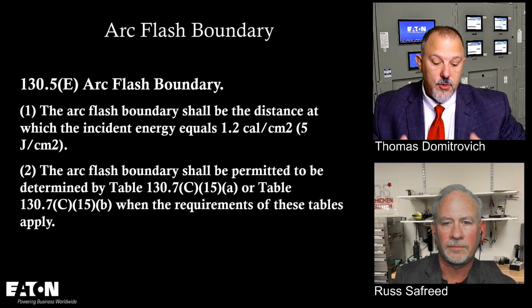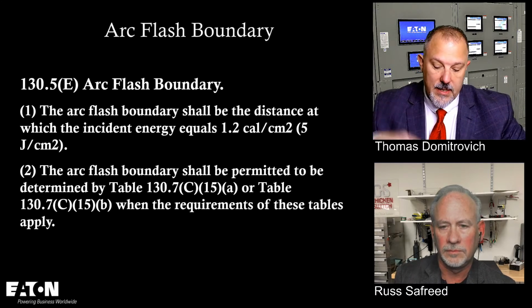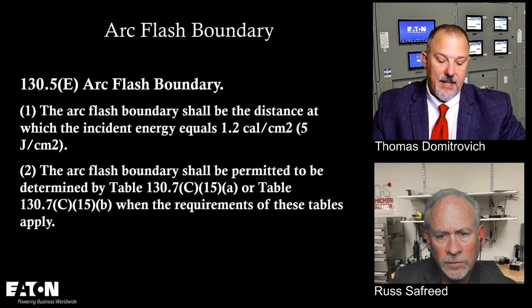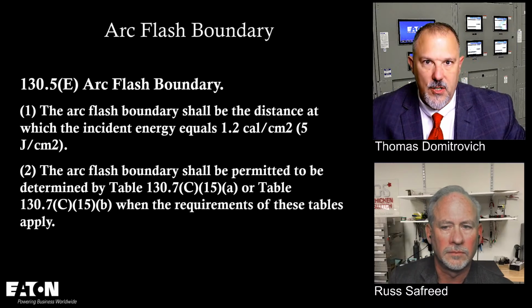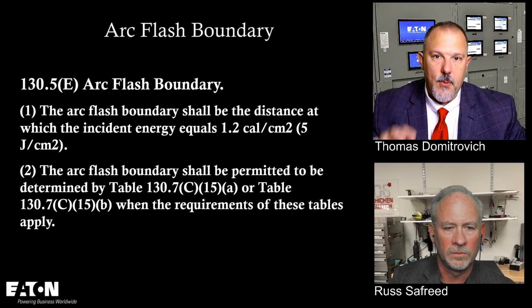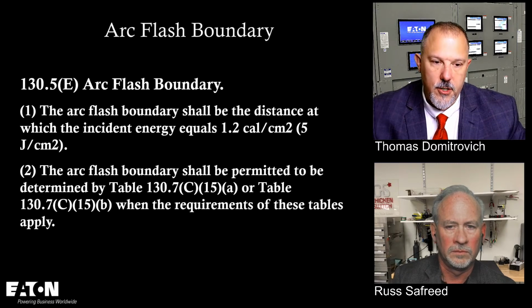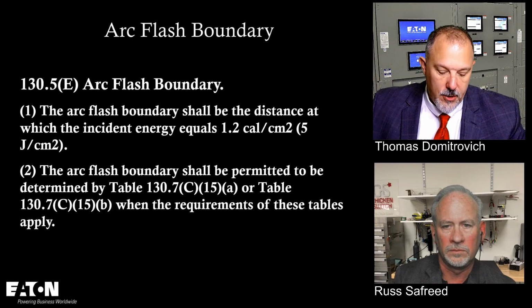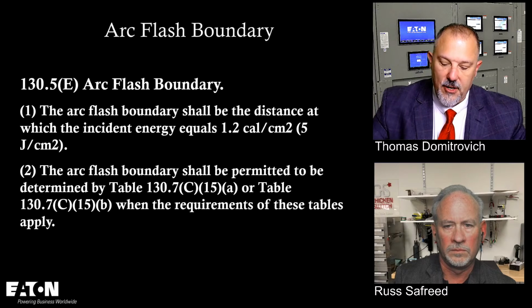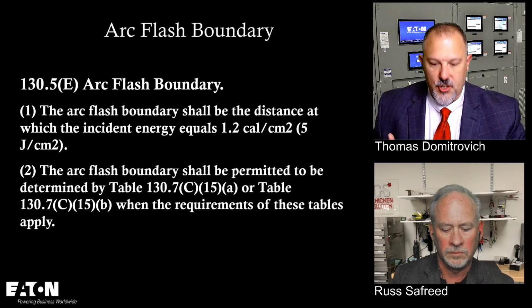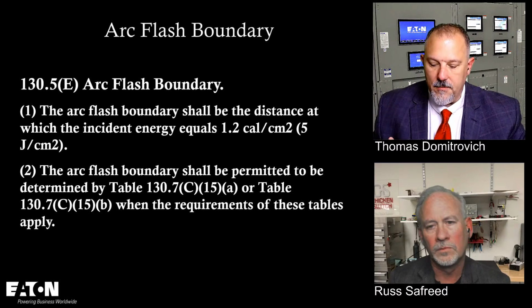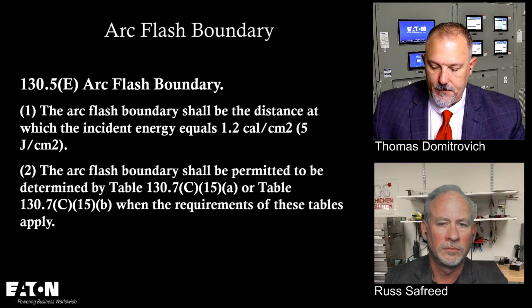They'll use 130.7(C). What this table does is it gives you all the different types of equipment and some parameters: voltage, available fault current, and what the upstream overcurrent device is. And it tells you the arc flash PPE category, so it tells you how to dress. And then the next column is the arc flash boundary.